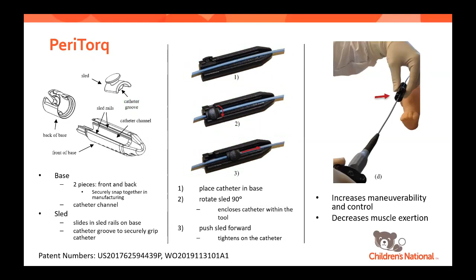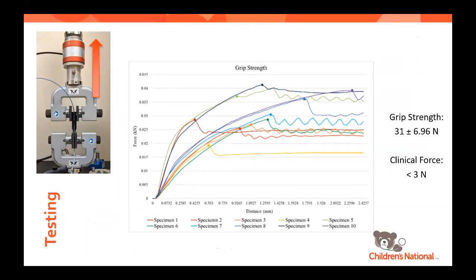We conducted 4 main tests of performance on the tool, starting with grip strength. The tool was placed on a standard 7 French ablation catheter, with the sled advanced to a predetermined location based on feedback from end users of expected normal use. The tool and catheter were set up on an Instron, and an axial force was applied to the tool until slip occurred. The tool began to slip at an average force of 31 Newtons, which is approximately 10 times greater than the peak force needed to insert a catheter into a vessel.